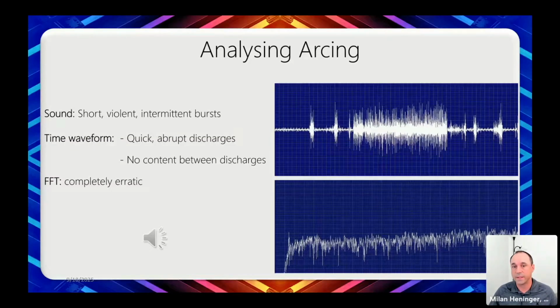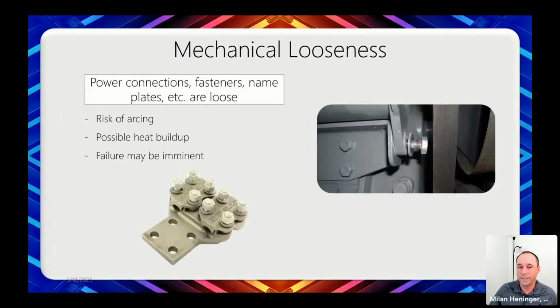Mechanical looseness is kind of the last one, and probably the one that I've seen personally a lot. This is where power connections, fasteners, nameplates are loose for some reason. It could have been improper torquing procedures. It could have been a mistake. There's a variety of things that can lead us there, but ultimately what we are trying to avoid is any risk of arcing, heat buildup, and imminent failure.